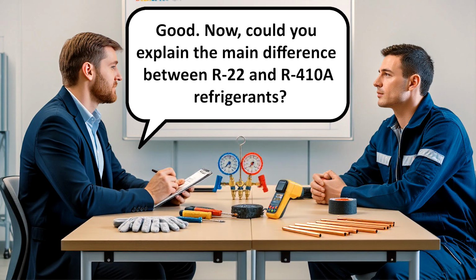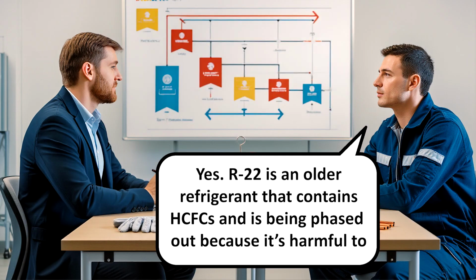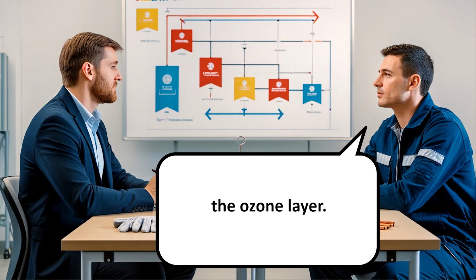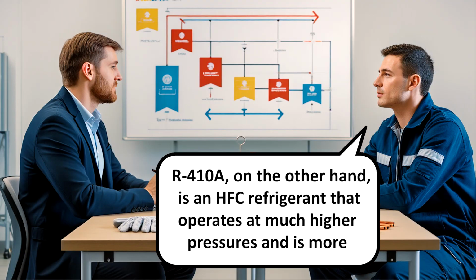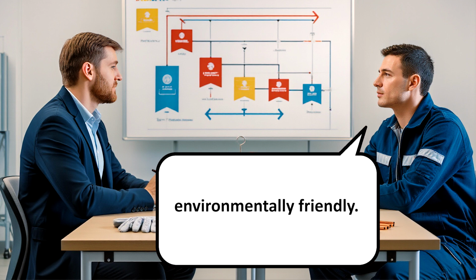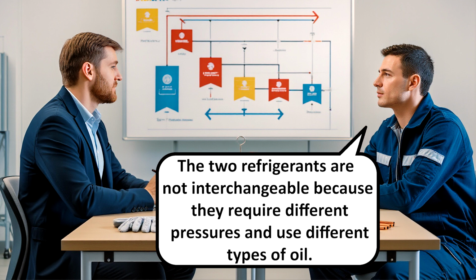Good. Now could you explain the main difference between R22 and R410A refrigerants? Yes, R22 is an older refrigerant that contains HCFCs and is being phased out because it's harmful to the ozone layer. R410A, on the other hand, is an HFC refrigerant that operates at much higher pressures and is more environmentally friendly. The two refrigerants are not interchangeable because they require different pressures and use different types of oil.